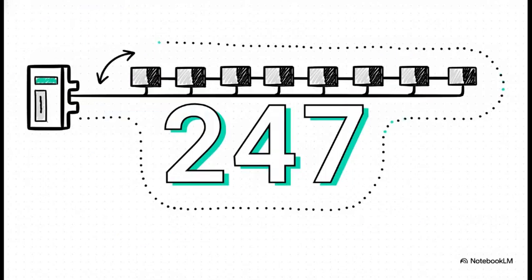And regarding that ADD parameter, the Modbus address, check this out. A single Modbus network can theoretically support up to 247 uniquely addressed slave devices. Yeah, 247. That means from just one single PLC master, you can control up to 247 distinct ATV320 drives, all on a single daisy-chained cable. It's pretty wild when you think about it.